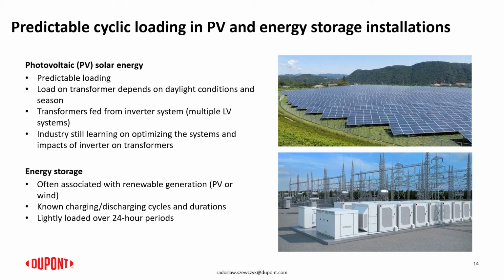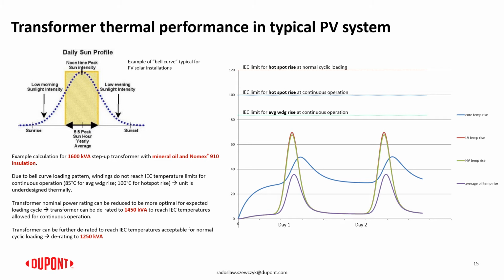And then moving to the photovoltaic systems, which I mentioned before, what is specific about them is the periodic and quite repetitive loading, and the loading cycle that may be evaluated based on the sun conditions in the area. What we know is that this repetitive loading cycle allows for the optimization of the transformer construction. This is an example of the typical bell curve in the photovoltaic systems when the maximum power capacity from the inverter system is available around noon.